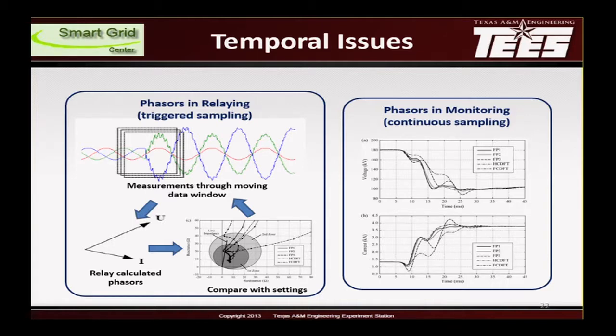We're measuring phasors in relays. If you know how a distance relay or impedance relay works, it is estimating a phasor. If you look at phasor measurement units, it is estimating a phasor. But what phasor? Because the signals are, in many instances, in relaying in particular, abruptly changing and have all kinds of components.